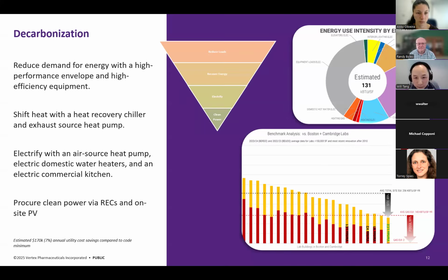Once we reduce the electric demand on the building, that's when we can move forward. First we reduce the demand, then we cover the heat with the heat recovery chiller, and then we electrify by using less fossil fuel. From there, yes, we've been shifting a lot of these emissions to scope two, but we can further reduce our scope two by procuring clean energy, as Randy mentioned earlier.